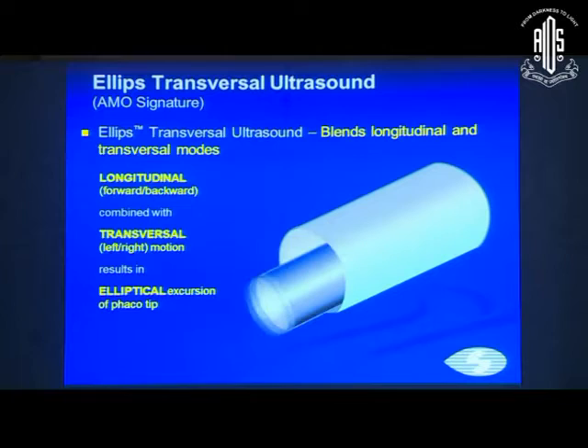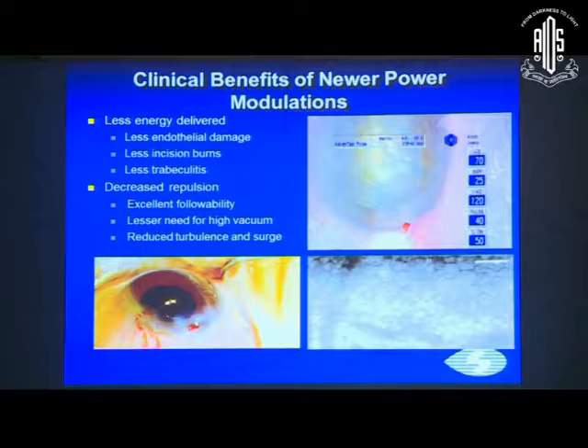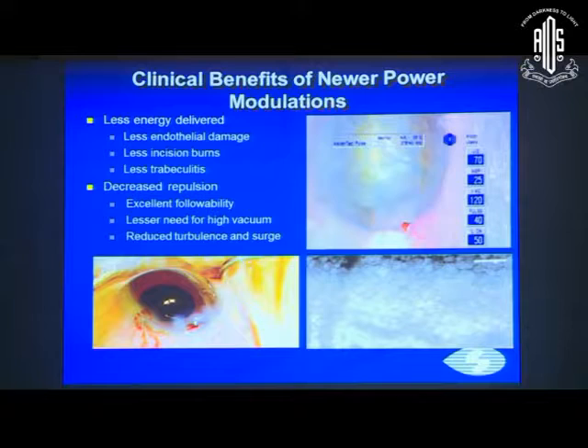This transversal ultrasound is present in the AMO Signature. The benefits include less energy delivered, less endothelial damage, less incision burns, and less iritis. There is also less repulsion of the nuclear fragment, which improves followability, reduces the need for higher vacuum normally required with longitudinal phaco, and reduces turbulence and surge.